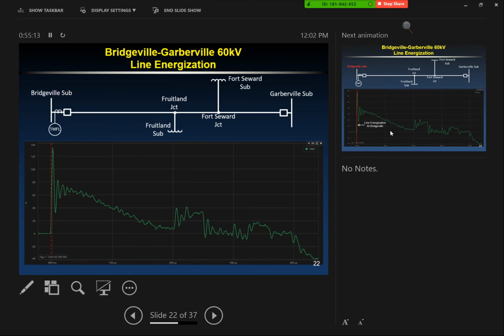You could drill down to looking at individual poles, and it's the basis for what we use to figure out the lengths between these points. So I could use that graphical system to know the distance between Bridgeville Sub and Fruitland Junction. That's what we go to whenever we're doing fault location. We know with our fault duty program what percentage of the line we expect the fault to be.